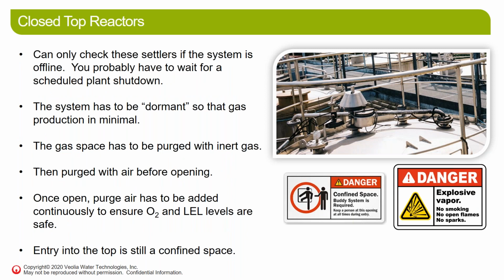So really, you can't go into this tank or open it up while the system's live. You need to shut down because it's closed and it's got that gas space. So again, like what Jill was saying, you've got to shut the system down and let the system go dormant so the gas production is minimal. You have to purge that space with inert gas. Then once the biogas and H2S readings coming out of that space are below LEL, below permissible limits, you can open these tanks and ventilate. And you pretty much have to keep it ventilated during an opening.